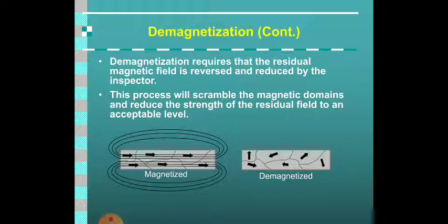The field should be gradually reduced to zero while undergoing cyclic reversal, and hammering and rotating in the field sometimes assist demagnetization as well. Annealing or stress relief heat treatment will demagnetize the steel weldment, and total demagnetization is always accomplished when the weldment is heated above the Curie temperature, 768 degrees for carbon steel.